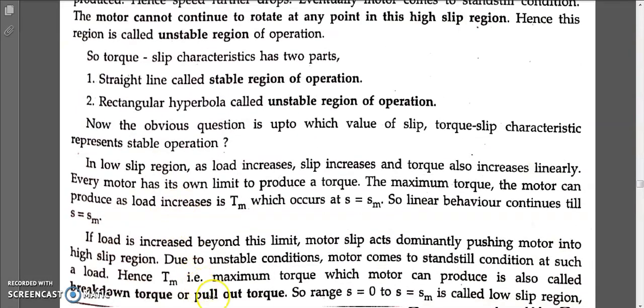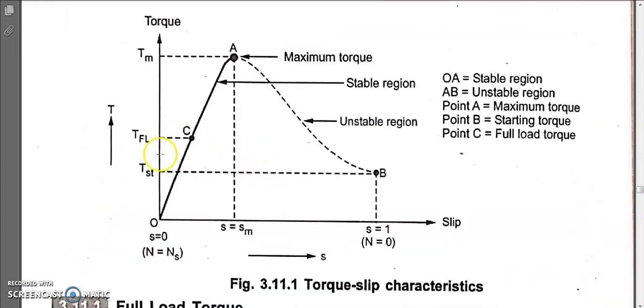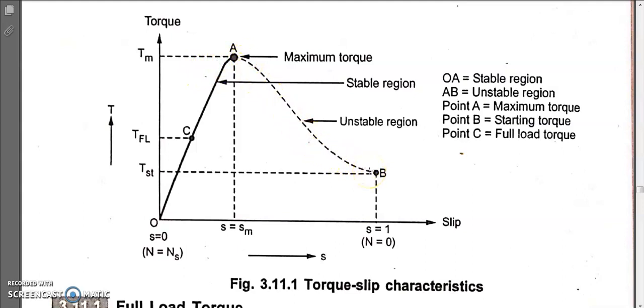From the diagram, we can see that the torque-slip curve has a straight line part and a rectangular hyperbola part. Region OA is the stable part and AB is the unstable part. In the unstable region AB, the motor slows down and eventually stops.